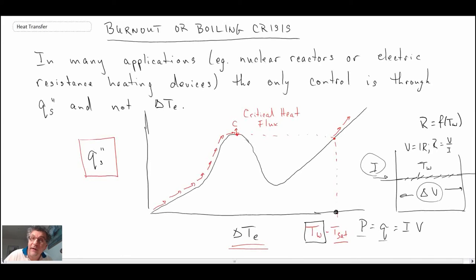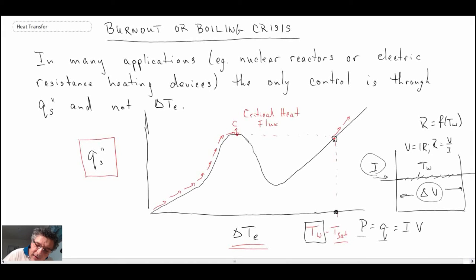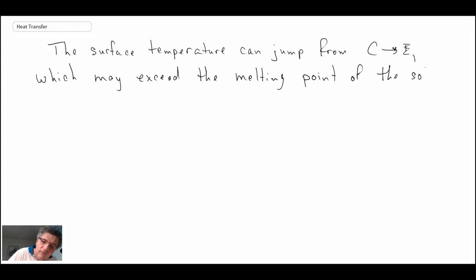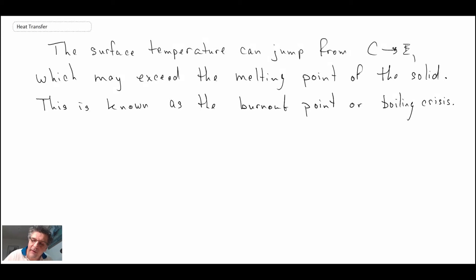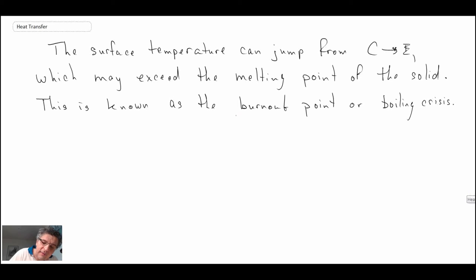Now, Nukiyama was very persistent, and I'll tell you how he got around this problem in a moment, but let me make a comment. So, the surface temperature can jump from C to E, and I didn't put E here, but this is E, and this was C. What happens is that we can jump from C to E. When we look at our boiling curve, we can quickly go from C all the way up to E, and this can exceed the melting point temperature of the wire, and that's why it's sometimes called the burnout point, or the boiling crisis. You do not want to operate your system there, because if you're exceeding the melting points of the material, it will melt down, and that happens with nuclear reactors, and it can also help it happen with electric resistance heating devices like Nukiyama was using.